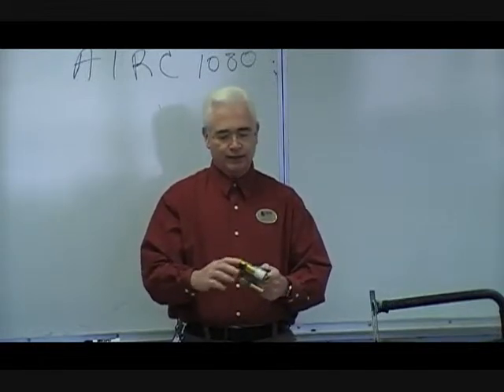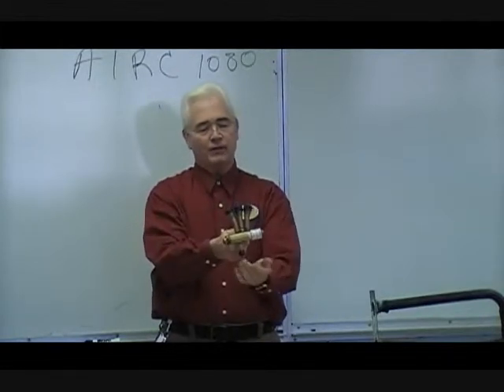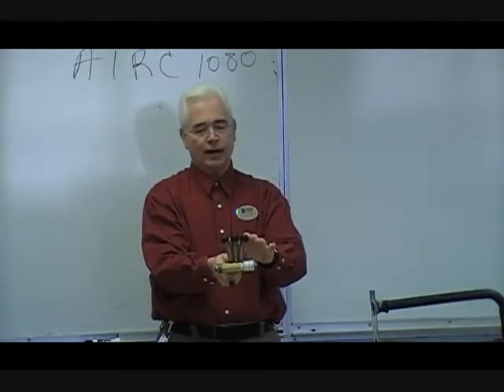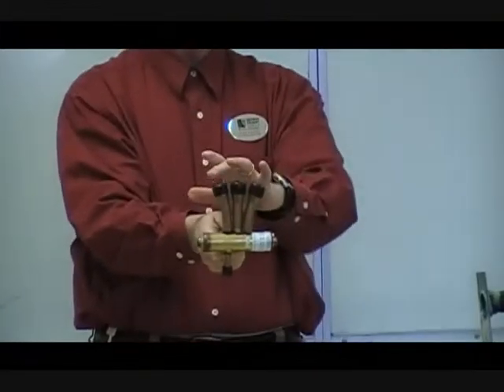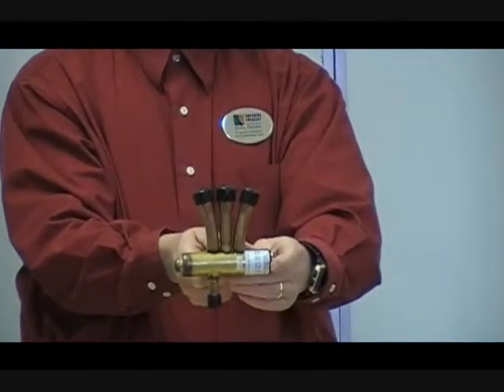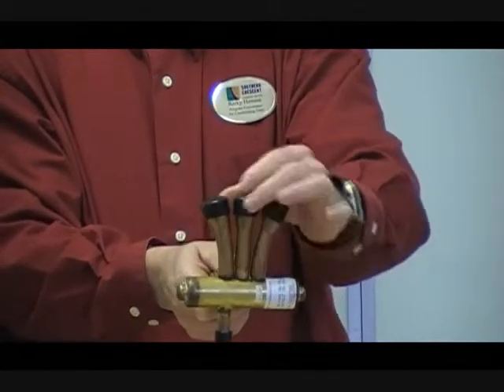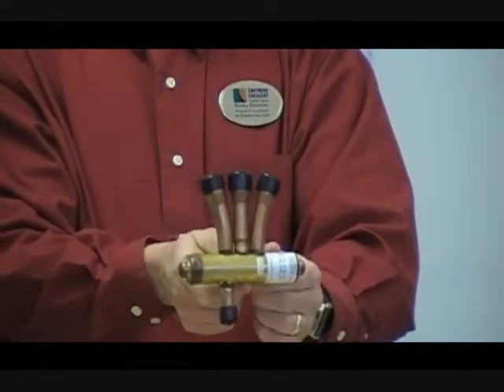The reversing valve is what makes the heat pump a heat pump. On the reversing valve, you've got four pipes — one pipe on one side and three pipes on the other side. The one pipe is always the discharge coming off the compressor, always. On the side with three pipes, the pipe in the middle is always the suction line going to the compressor, always — common discharge, common suction. The two outside pipes will switch position from suction to discharge depending on what mode the unit's in.